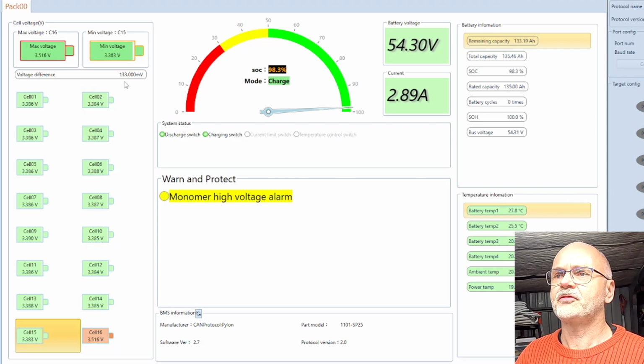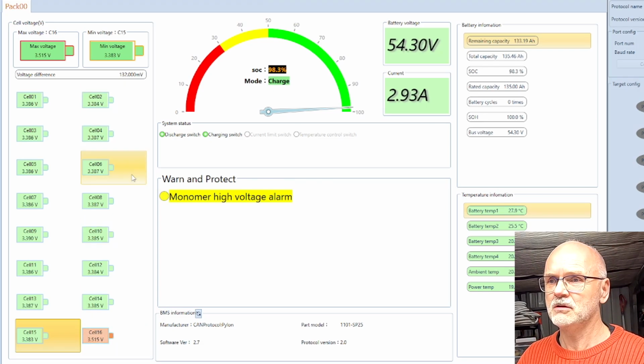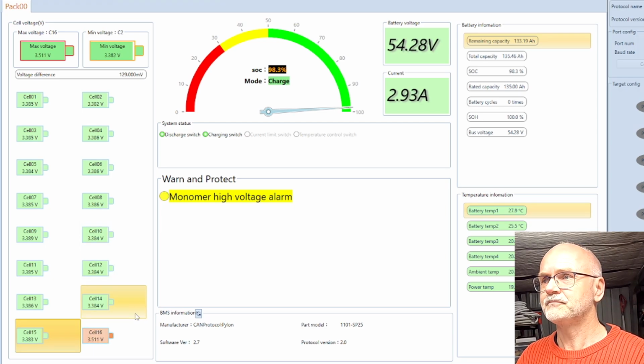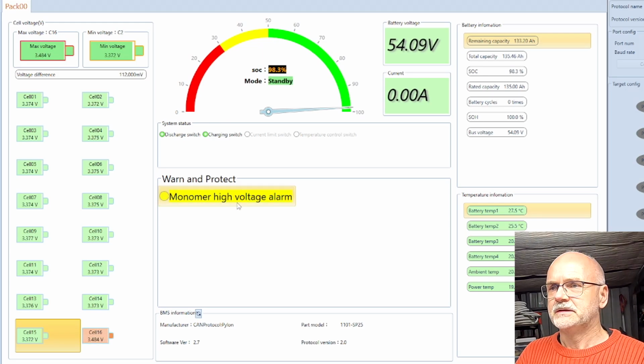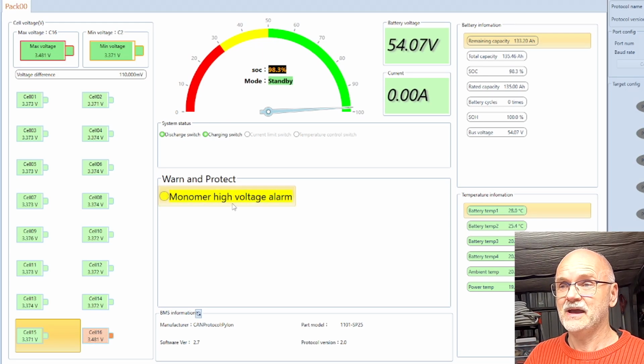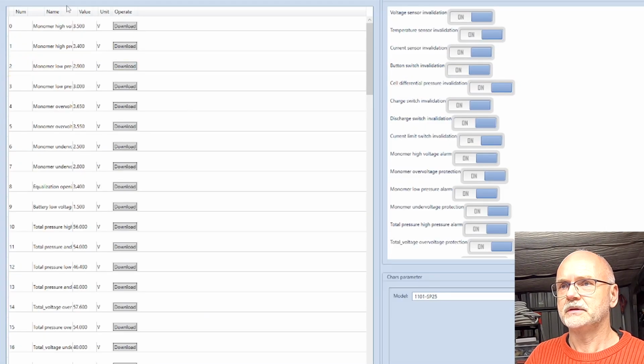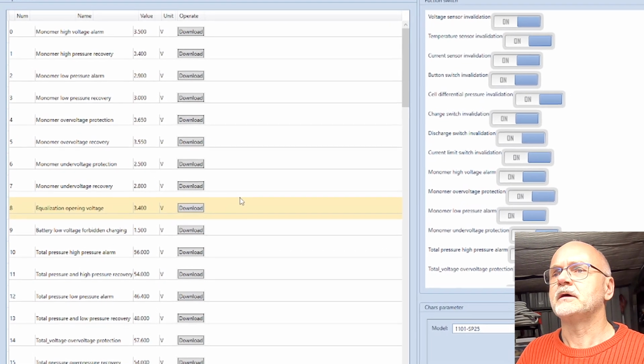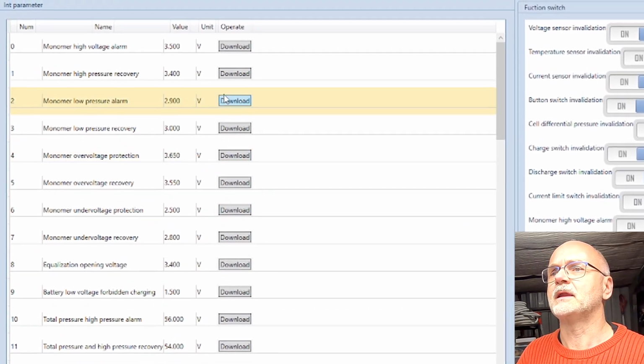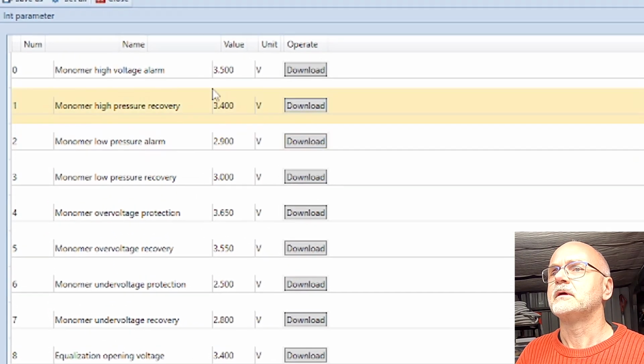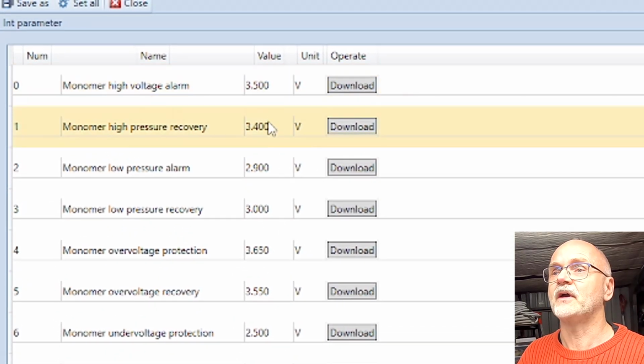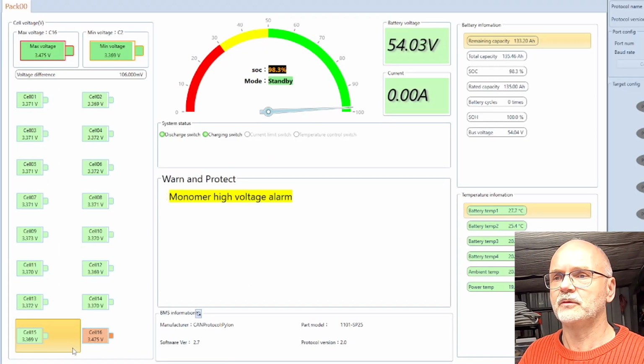See, we've got a 134 millivolt deviation now in the battery, but it claims we are at 98.3% state of charge. So at the moment we only have a high voltage alarm on one of the cells, and this is so annoying. Okay, the high voltage alarm triggers at 3.5 and clears at 3.4 again. And this is exactly what we can see here now.